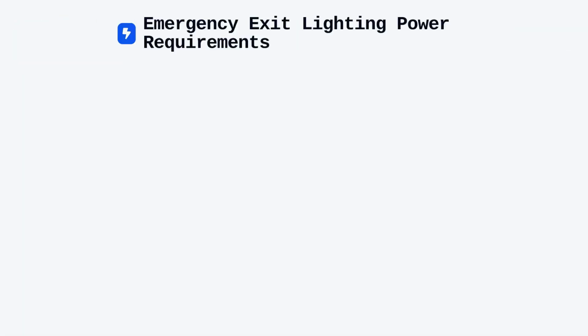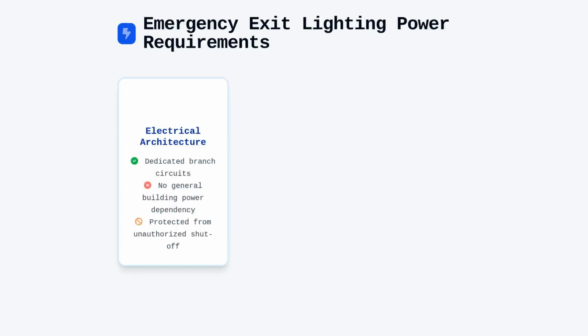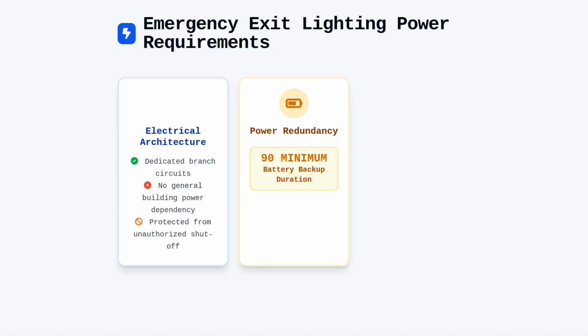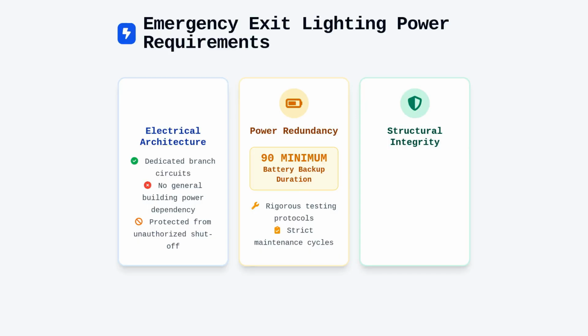Power reliability is a significant design constraint that requires deep consideration of the electrical architecture. Exit signs cannot merely rely on the general building power because a fire event often involves utility failure or circuit breakers tripping. Therefore, these systems must be connected to dedicated branch circuits that are not susceptible to being switched off by unauthorized personnel. Beyond the main power, there is a mandated requirement for emergency power, typically provided by battery backups that sustain the sign for a minimum of 90 minutes. These batteries are subject to rigorous maintenance and testing protocols to ensure they do not fail the moment they are needed. We often overlook the structural aspects of these signs, but they must be securely fastened to prevent them from becoming hazards during seismic events or mechanical failures within the ceiling assembly.